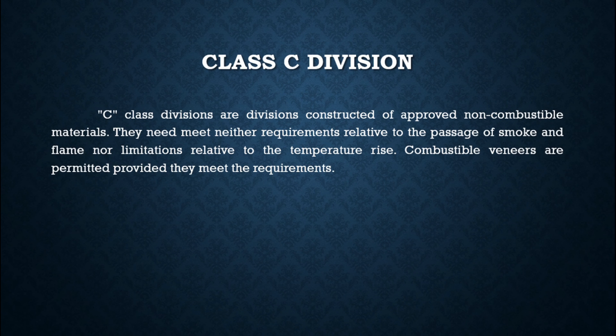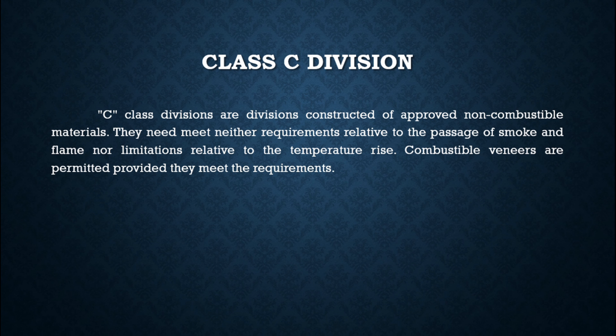Class C divisions are constructed of approved non-combustible material. They need not meet any requirements related to the passage of smoke and flame, nor limitations relative to temperature rise. Combustible veneers are permitted provided they meet the applicable requirements.